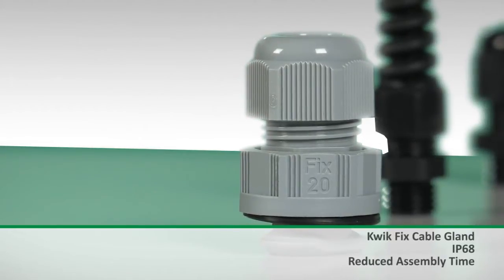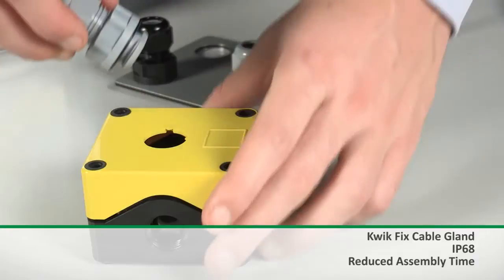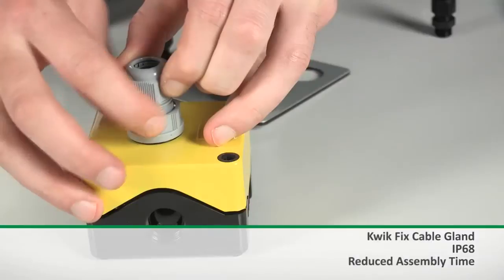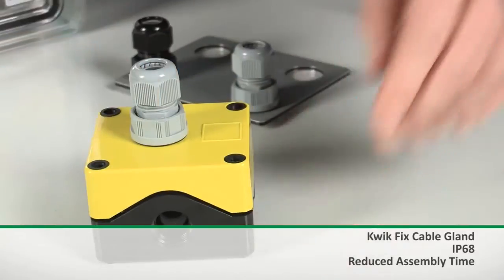The Kwik Fix cable gland has been designed to offer installers speedy installation on applications where they've only got access to a single side of a panel. Using the specially designed footplate at the end of the gland, it's inserted into the panel of the enclosure and then pulled against the internal wall. The gland is then screwed down, which creates an IP68 seal and gives full protection to the internals of the housing.